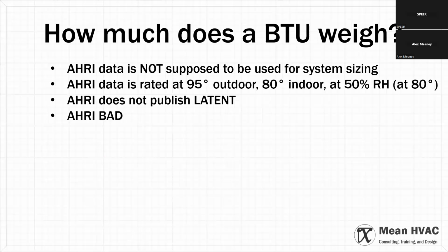So the second I put a system in Texas, it's performing worse than the AHRI ratings, okay? Because AHRI rated under these, in my opinion, stupid conditions, right? I agree with their outdoor, but the indoor ones, gosh. So in order to properly select a piece of equipment, you have to start with the manufacturer data.